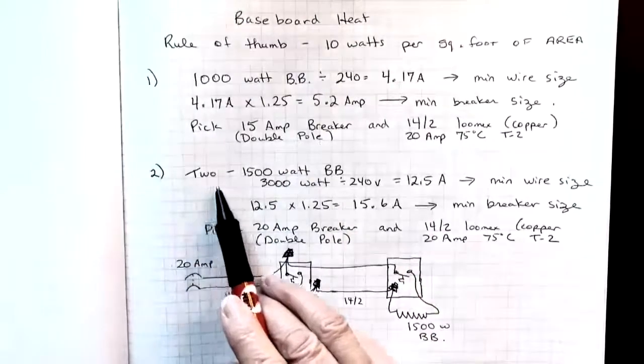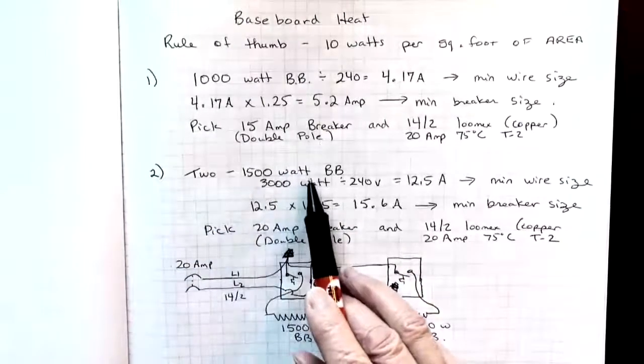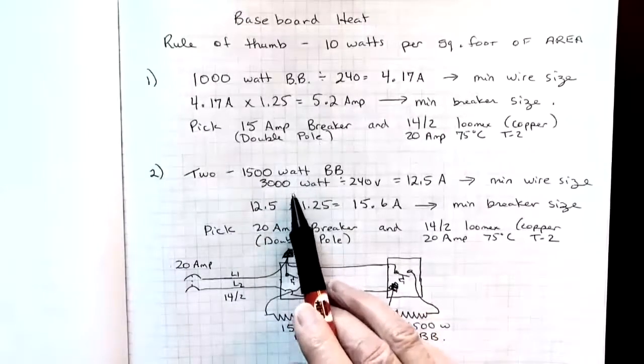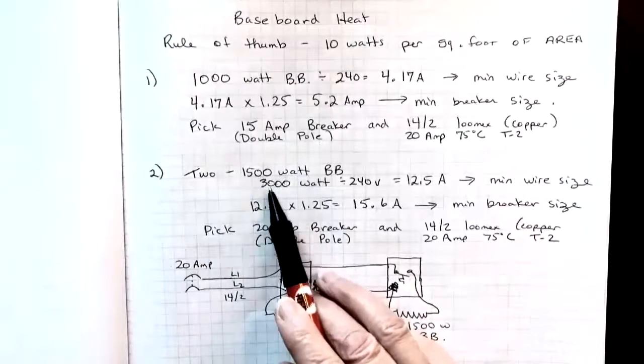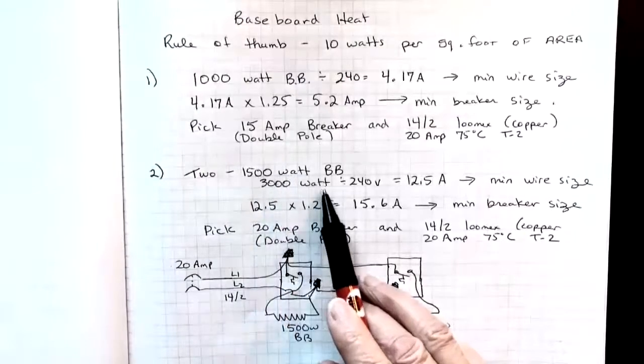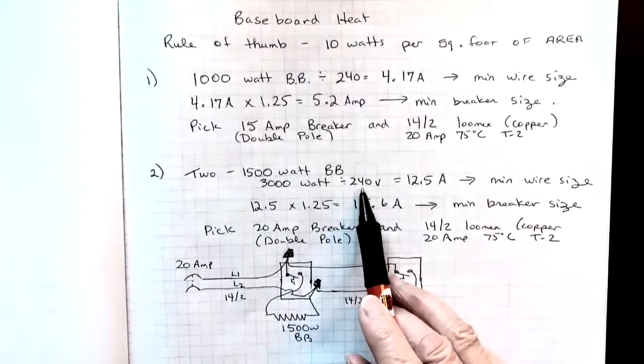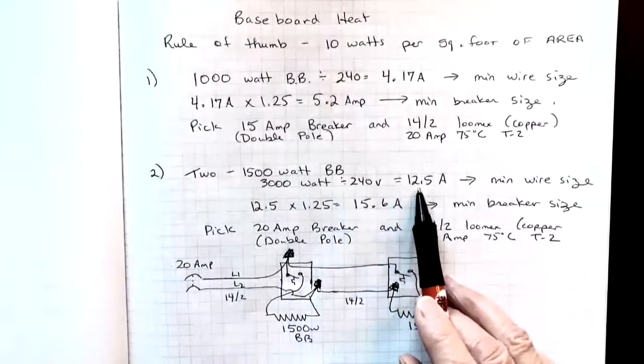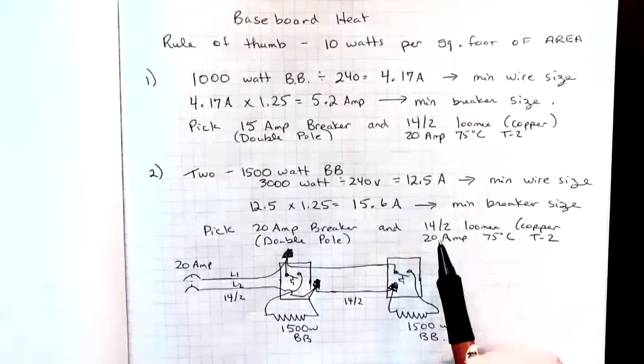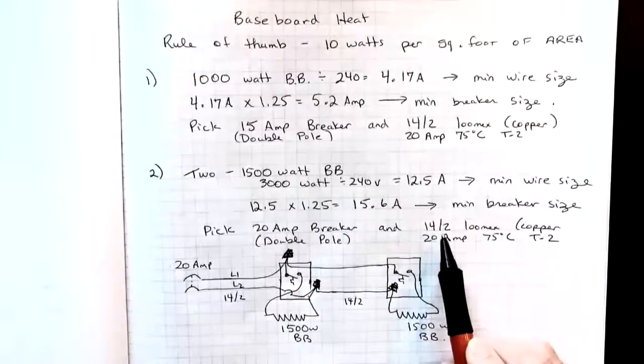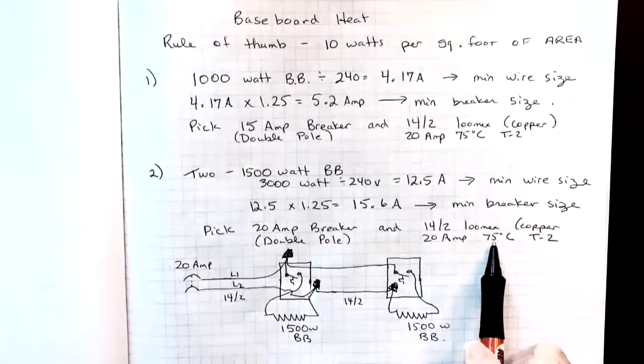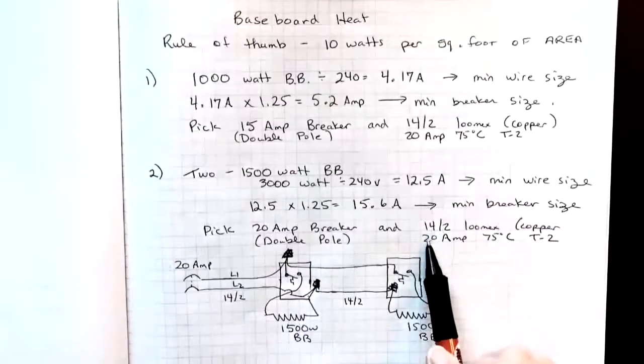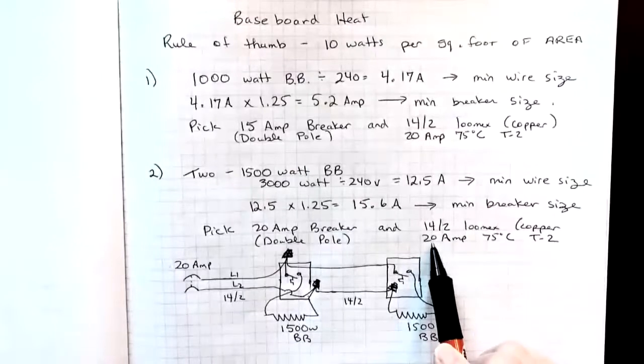Our second example is two 1500 watt baseboard heaters. Let's say we were putting these on a circuit in a large rec room. So 1500 watts times 2 gives me 3000 watts in total. Again, I'm assuming these are 240 volt baseboard heaters. So divide by 240 gives me a minimum ampacity for my wire of 12.5 amps. Again, looking down here, if I went to table two in the 75 degree column, I could choose a 14/2, which is good for 20 amps.